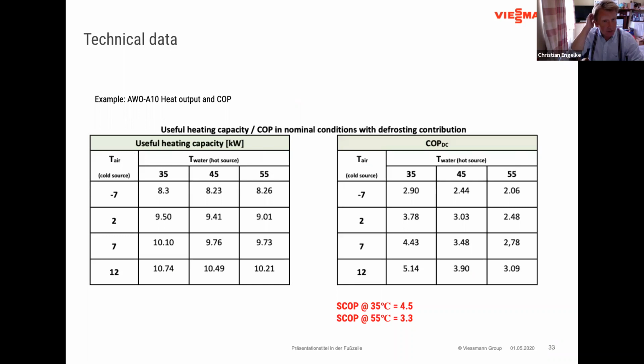More information about the COP, I've discussed at length in the other session, but here I just give you again an overview of how the efficiency and the outputs change by selecting a different operating mode. So this is just for the 10 kilowatt machine. In here we have the hot water temperature, 35, 45 and 55. And here on the left hand side, this is the air temperature. And these are our test points: -7, 2 degrees, +7 degrees, and +12 degrees.